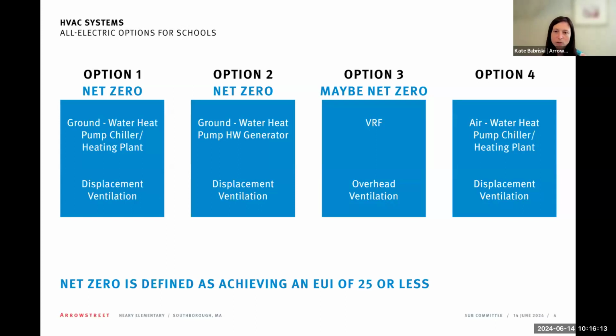Again, we're defining net zero as an EUI of 25, which is a benchmark established through the Mass Save program, as well as other national benchmarks for schools. Option 3 is a VRF system, essentially an air source heat pump that's using the air as the heat transfer instead of the ground. The air temperature obviously has wide fluctuations from very cold to very warm, so it's not quite as efficient, but heat pumps in general are quite efficient. And that's why it says maybe net zero, because this sometimes really can't get quite to the 25. It might end up being like 26, 27. And so that's why it says maybe net zero.